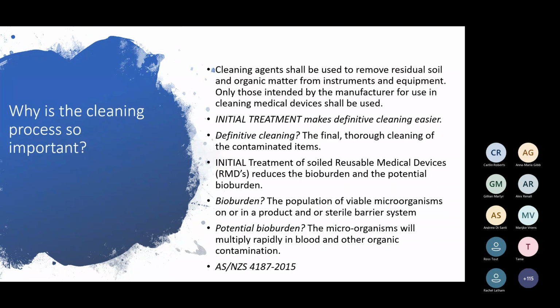So why is the cleaning process so important? Cleaning agents, now, because I've taken some of this wording straight out of the standards, whenever you hear somebody use the term shall, it is a mandatory requirement. If you hear the word should, it's a recommendation. So when I say the word shall, it means this is what you have to do. Cleaning agents shall be used to remove residual soil and organic matter from instruments and equipment. Only those intended by the manufacturer for use in cleaning medical devices shall be used. So once again, you can't use, you know, Palmolive from the supermarket. You have to use a detergent that has been specifically approved by the ARTG.